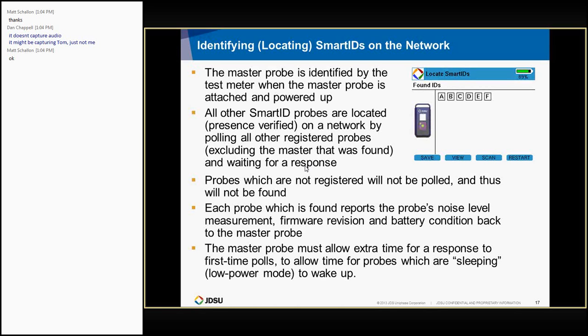So it does take a few seconds for it to go through this test. If you have more than 10 probes, it'll probably take maybe a dozen seconds or a little more to actually scan all of them. It has to allow some extra time for response to first-time polls, because these probes will go after 30 seconds of idle time. They'll go into a standby state where they only wake up once every 5 seconds for a tenth of a second or so to check for any traffic and to see if anybody's trying to talk to them.